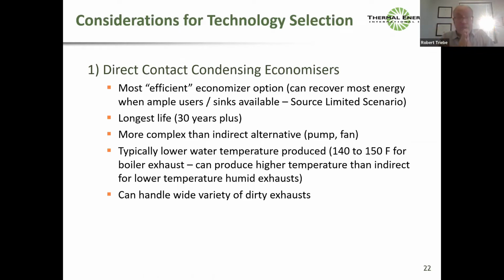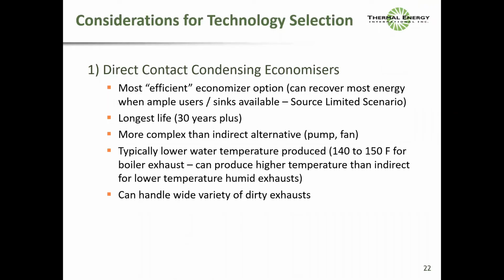Sorry about that. But if you recirculate the water, so now I'm recirculating, it's not once through. The worst case is you reach a pH of about 4.5 because of the absorption of CO2, which creates carbonic acid. So that circuit would be stainless steel or even PVC or CPVC. PVC is kind of low on the temperature end. But the short answer is, in a recirculating system, you will become slightly acidic, carbonic acid. So we typically have those circuits in stainless steel. On a once through, it's potable. On a recirculating system, you may need some pH adjustment, but at the same time, if you're using stainless steel, the pH of 4.5 and carbonic acid is not an issue. So is that okay for the question, Mark? Yes, absolutely. Thanks.